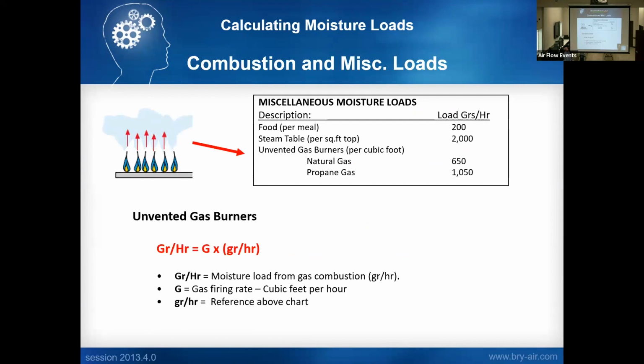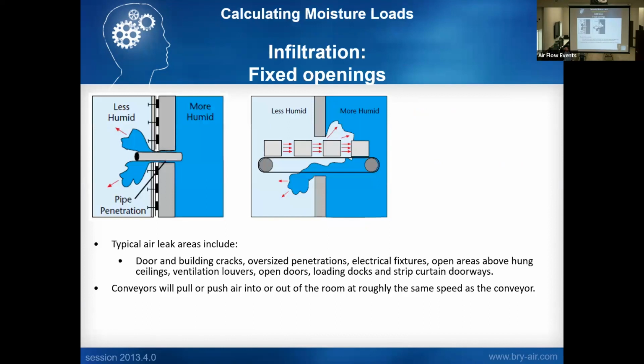the tank. Gas burners, again, direct fire flame in a room is going to add moisture. Whether it's natural gas, propane, typically they're from like forklifts, again, indirect or direct fire gas heaters in the space. Fixed openings, you see a couple examples of a room. You got pipe penetration, conduit penetrations, any type of penetration going through that room. And as we talked about conveyors, and you can kind of see here the less humid space, you can kind of see just the normal infiltration of the more humid space infiltrating into the less humid space in both examples.